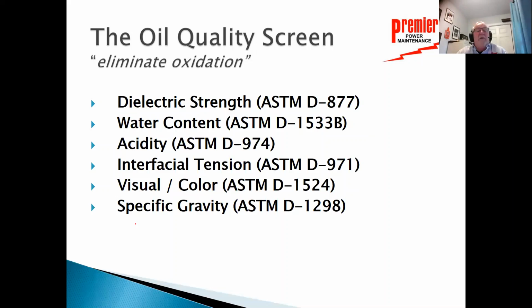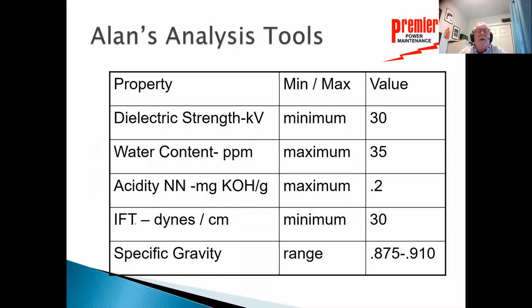So here are the tests we're going to do. We're going to do a dielectric strength, which is a kV test. We're going to do a water content. We're going to look at acid. We're going to look at interfacial tension. We're going to look at visual and specific gravity. All those tests. And again, all we're doing is looking at the quality of the oil in that transformer.